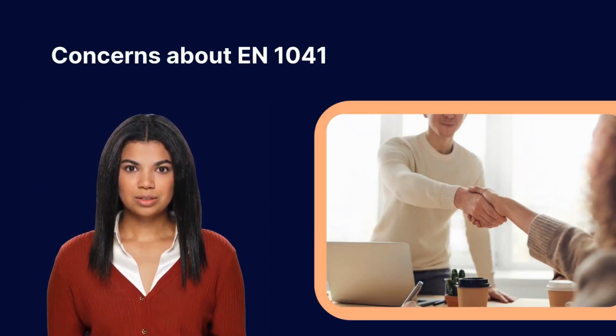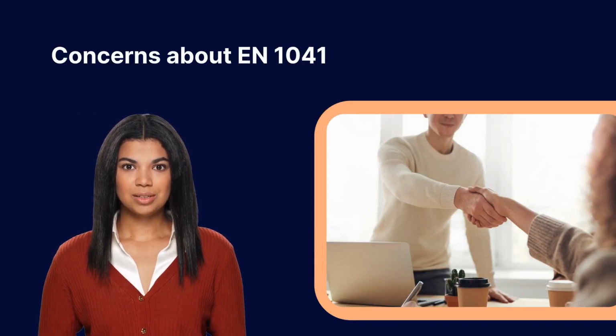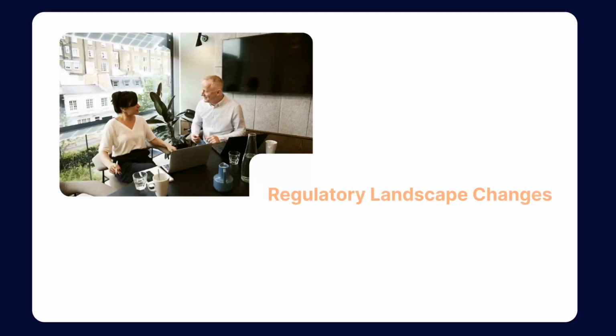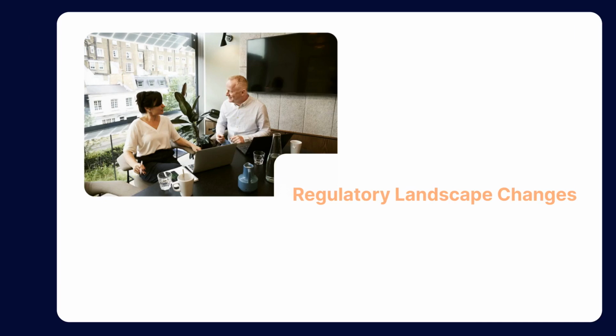However, over time, certain issues and constraints became evident. Some of the most important ones were: regulations have changed a lot in the medical device business, especially since the new European Medical Devices Regulation, MDR, and In Vitro Diagnostic Medical Devices Regulation, IVDR, came out. Initially, EN 1041 aligned with the MDD and IVDD, however, it necessitated updating to adhere to the more rigorous standards imposed by the MDR and IVDR.